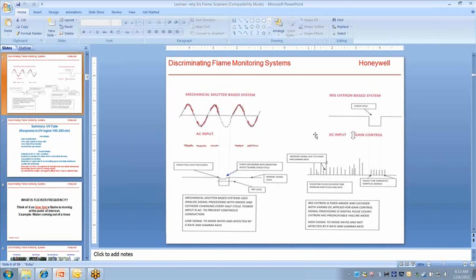Now, in some Honeywell tube literature, they will say that at a certain time you should replace it. The reason is that most of the Honeywell equipment before the Iris came in is non-adjustable gain, so they are fixed gain scanners. And when you have a fixed gain and you lose a little bit of sensitivity in the tube, it just goes downstream after that. It keeps on decreasing.